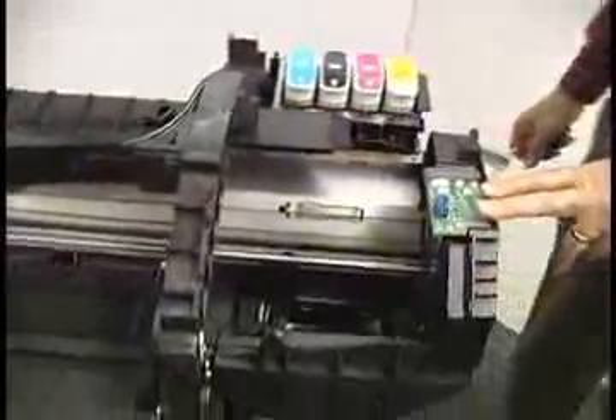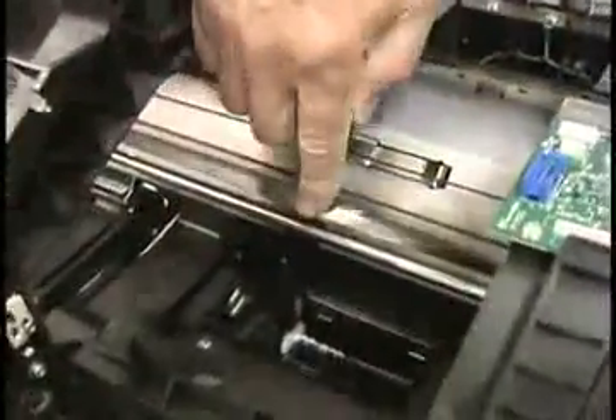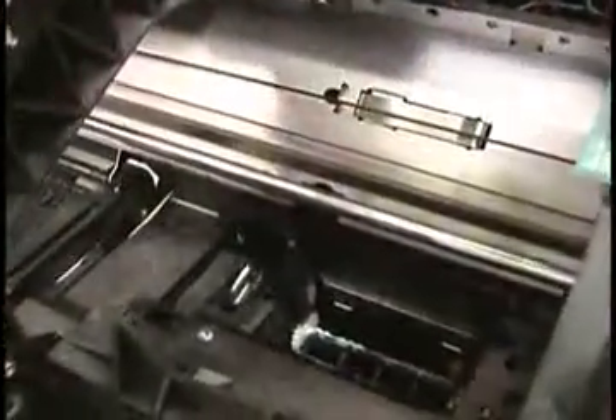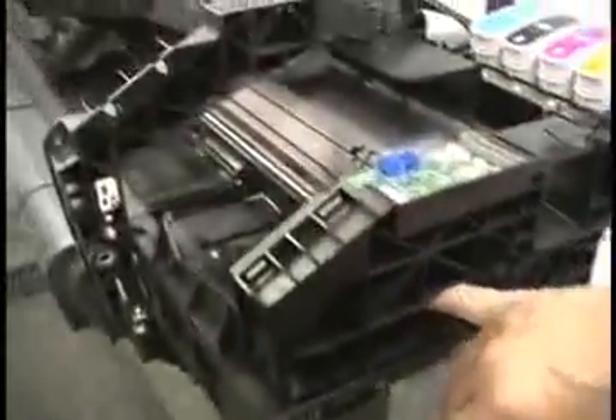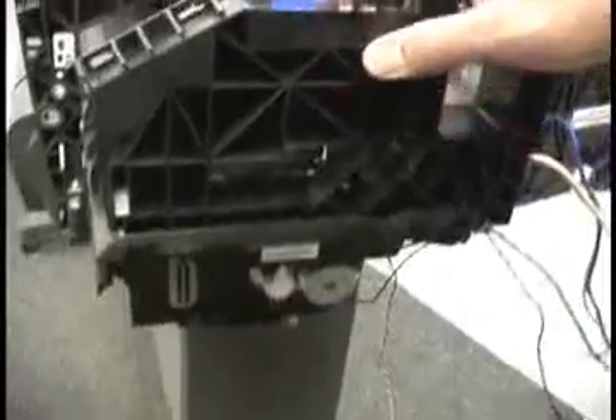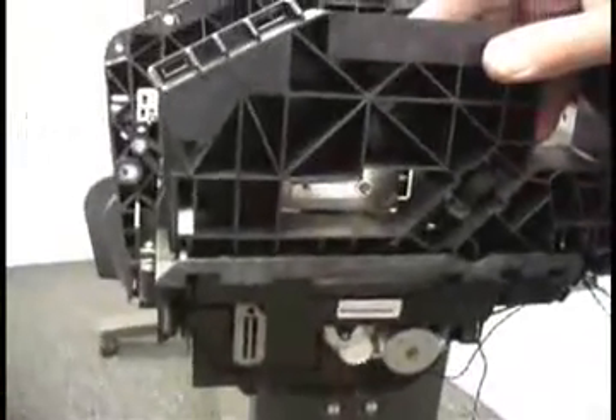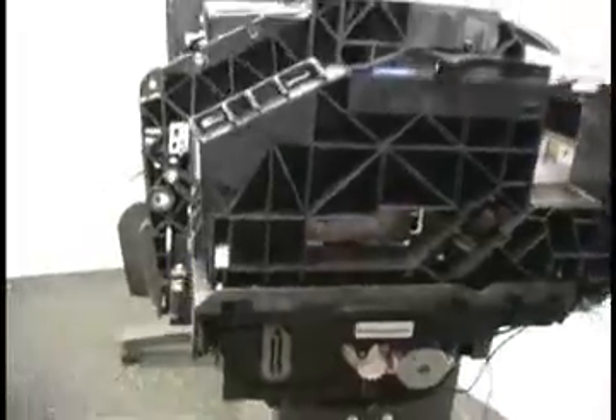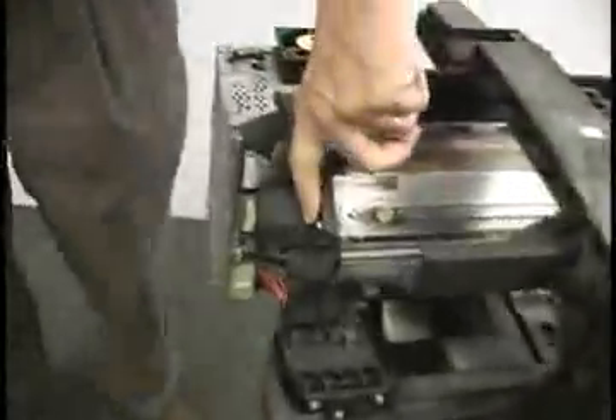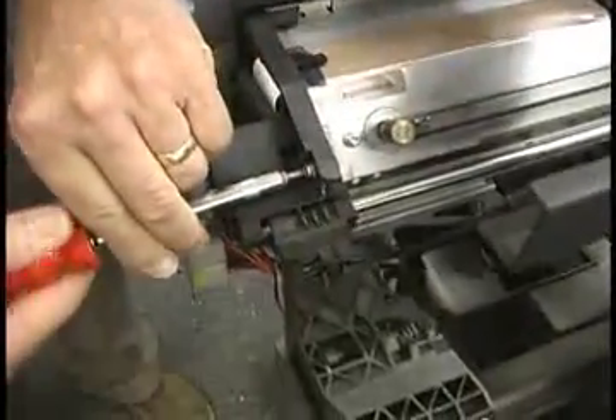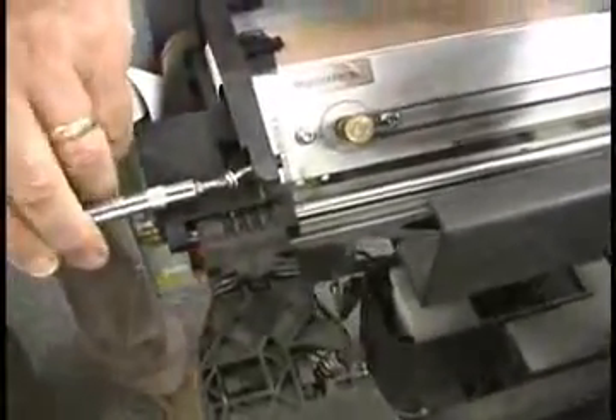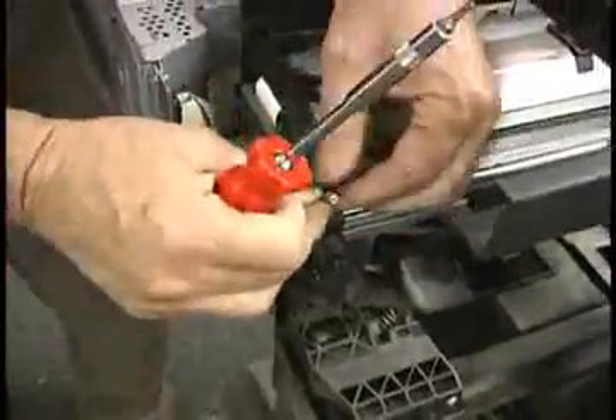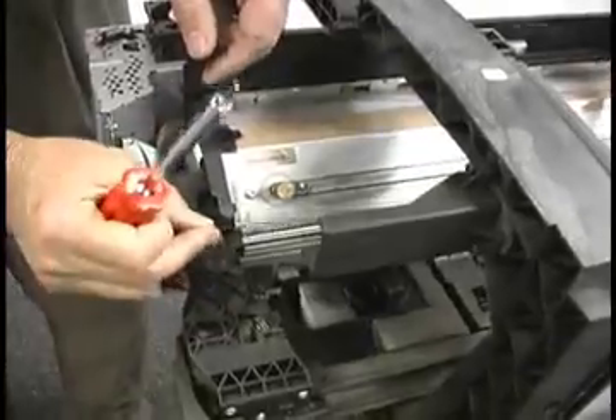Okay, we need to get the encoder strip loose. The encoder strip is this strip right here. It goes the full length of the machine. And it's a little bit tricky to get it back on this side if you haven't done it before. So what I'm recommending that you do is take a variation from the instructions and release it from the other end. There's one screw on that end we'll take loose. This screw right here, and loosen that. And sometimes it pops loose like that, sometimes it doesn't. You may have to pull it off.